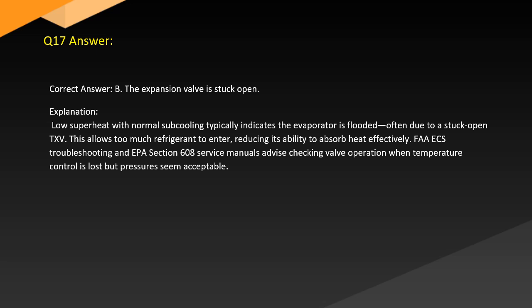Answer. Correct answer. B. The expansion valve is stuck open. Explanation. Low superheat with normal subcooling typically indicates the evaporator is flooded, often due to a stuck open TXV. This allows too much refrigerant to enter, reducing its ability to absorb heat effectively. FAA ECS troubleshooting and EPA Section 608 service manuals advise checking valve operation when temperature control is lost, but pressures seem acceptable.